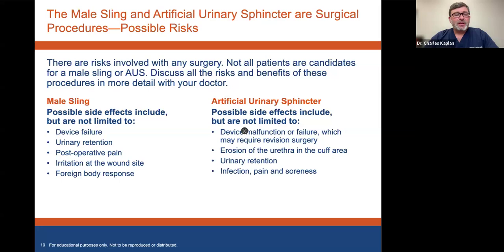The most common thing, though, that does happen with artificial sphincters, and it's not on here, is called cuff atrophy. And since that cuff is squeezing the urethra 24 hours a day, the tissue will start to shrink up. And when that happens, it's no longer tight enough and you'll start leaking. On average, that takes about 6 or 7 years. And when it does happen at that time, then what we typically do is we have to replace the device, replace everything.